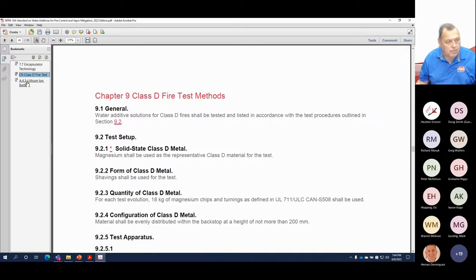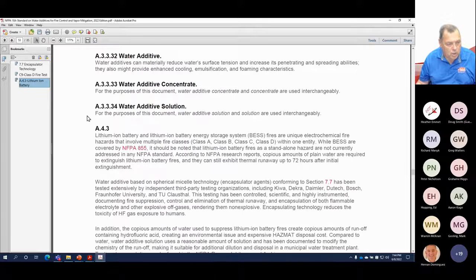The last thing I want to show is that this standard talks about lithium-ion batteries. Lithium-ion battery and lithium-ion battery energy storage system (BESS) fires are unique electrochemical fires involving Class A, B, C, and D within one entity. While battery energy storage systems are covered by NFPA 855, lithium-ion batteries as a standalone hazard are not currently addressed in any NFPA standard.